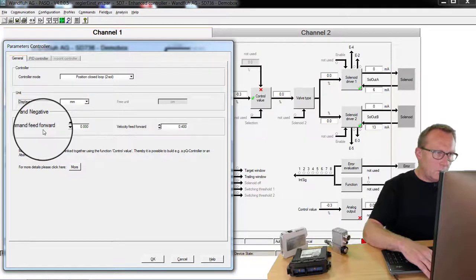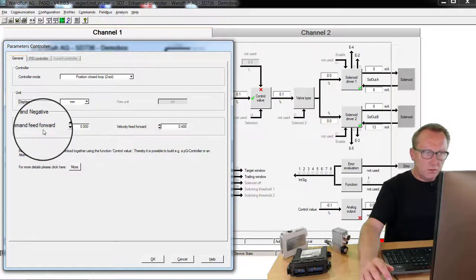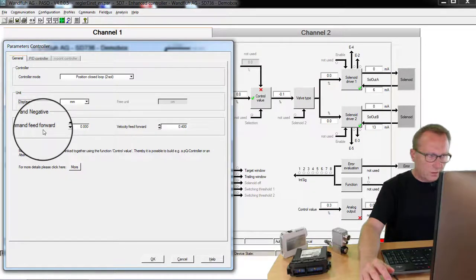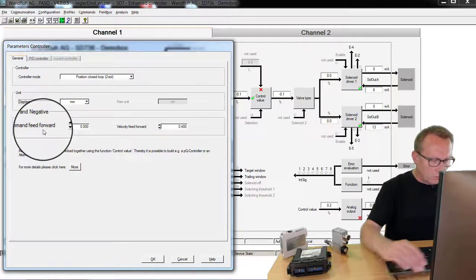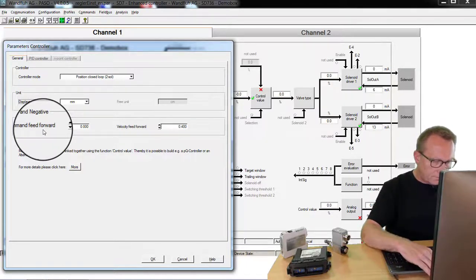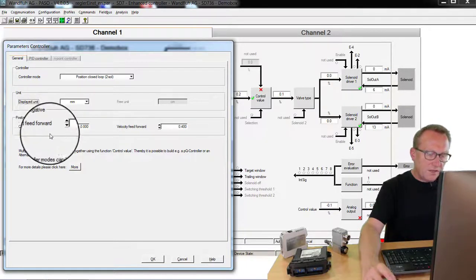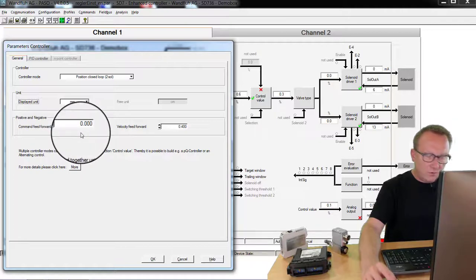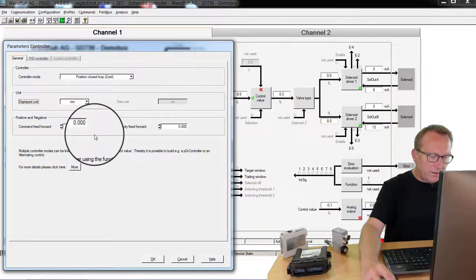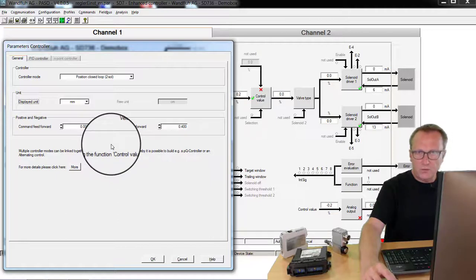The parameter command feedforward is used only for one solenoid closed loop systems, pressure or flow controls. And this parameter leads the command value direct to the valve. And then the controller has to make only the fine adjustment.